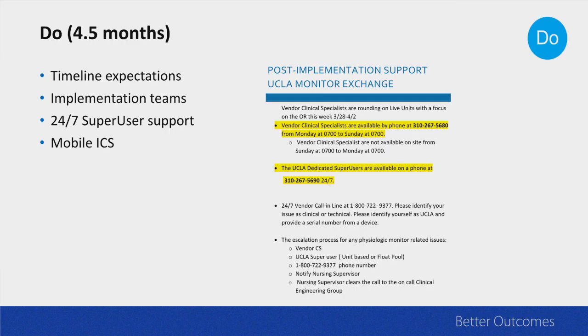Our classroom model was based on our EPIC model: every person who attended had their own monitor and each room was fully integrated to represent a patient unit. We had to convince staff that moving a patient from one unit to another using a smaller monitor would actually transfer the data. We had two central stations mimicking each unit so staff could shift their patient from one unit to the other. It helped them understand the flow — beyond just the buttonology of the monitors and patient safety items.